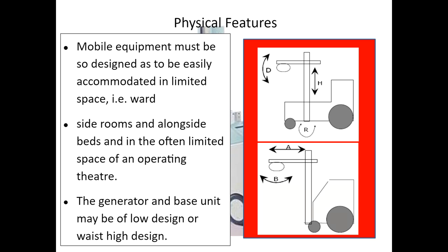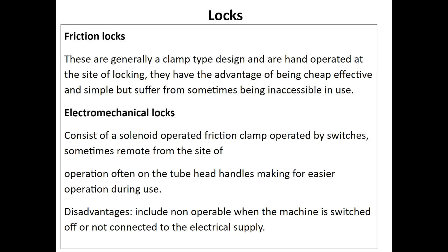Generator and the base unit can be either high or low frequency. Most of them are higher frequencies. The locks have gotten easier. When I did the demo for you, we talked about friction locks. Friction locks don't really exist anymore. You would put the tube in a certain place and then kind of screw it in, and it used friction to keep it in place. Now they're electromagnetic, you just let go and it stops, which is great. I mean, every year things get even easier.